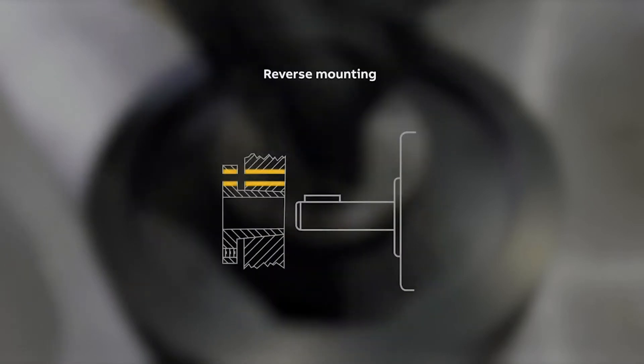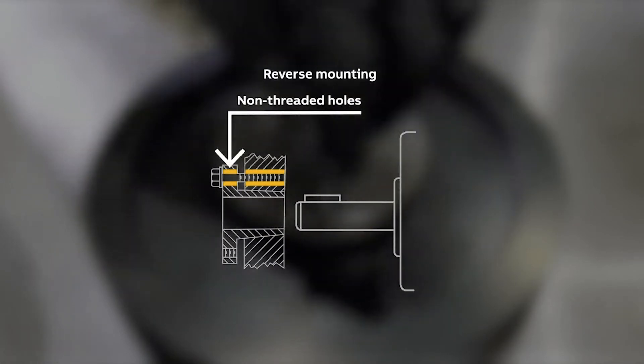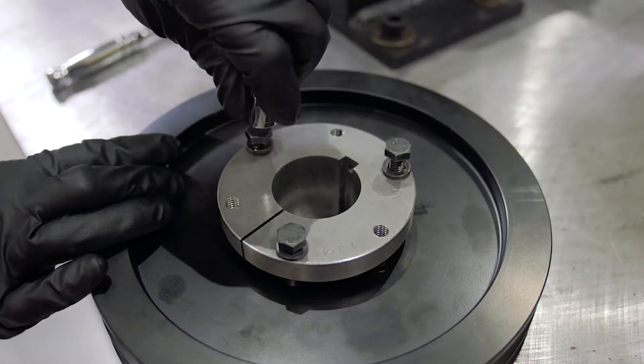For reverse mounting, align the holes so that the bolts can be placed through the non-threaded holes in the bushing and into the threaded holes of the hub. Loosely install all bolts and washers.